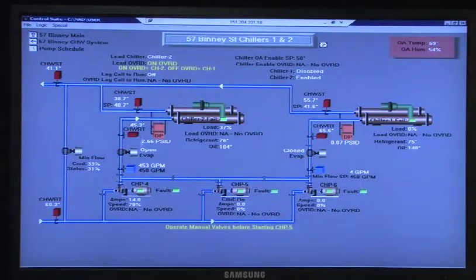Are those flow switches there, or are they just meters? Those are ultrasonic meters, aren't they? They're ultrasonically measuring the flow. It's not an actual paddle. That's not tied into the lockout. You're talking about the DP switch of the chiller itself. You're talking about a GPM flow meter. Two different systems. You want a proof of flow? Yes. Proof of flow is within the chiller. That chiller will not start if it doesn't have proof of flow.